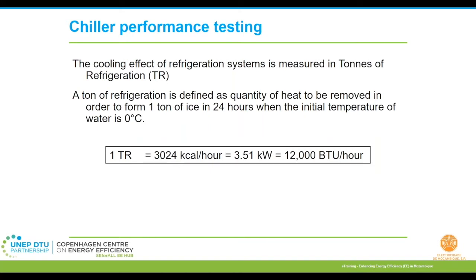So before moving on, the basic terminology which everyone should be aware of when it comes to HVAC systems is the cooling effect. These are the terminologies that they usually use for day-to-day activities. Here we talk about TR, that is tons of refrigeration. It is defined as the quantity of heat that needs to be removed in order to form 1 ton of ice in 24 hours when the initial temperature of the water is zero. In simpler terms, 1 ton of refrigeration is equivalent to about 3024 kilocalories per hour heat content wise. It is also equivalent to 3.51 kilowatts or 12,000 BTU per hour.